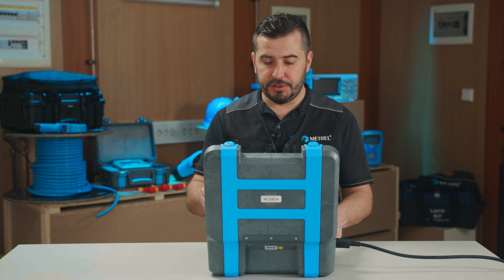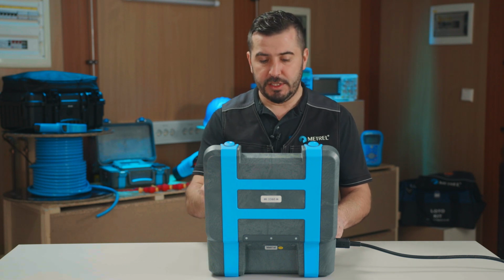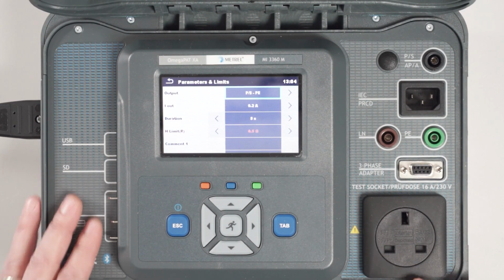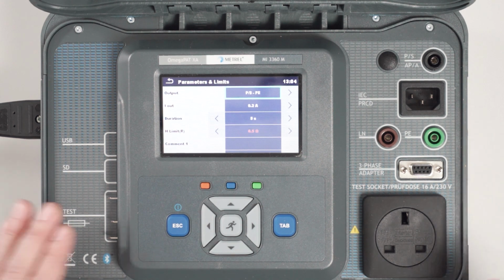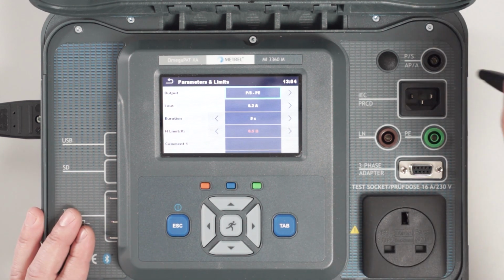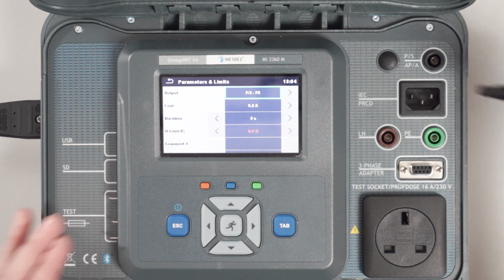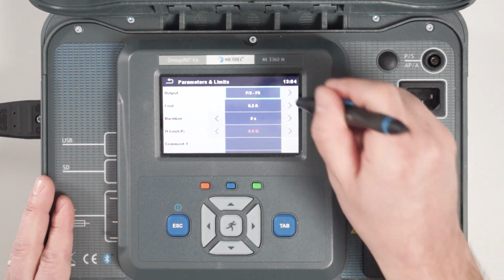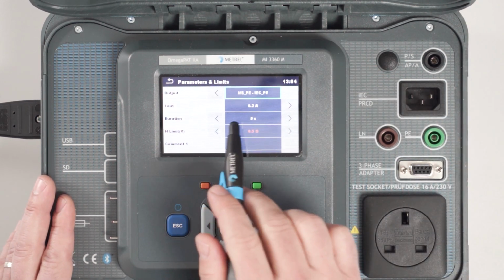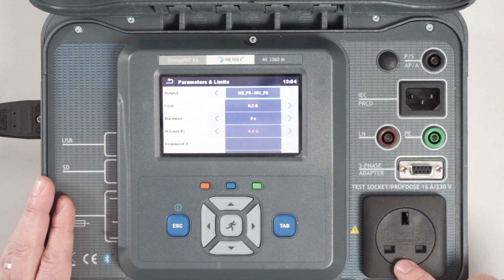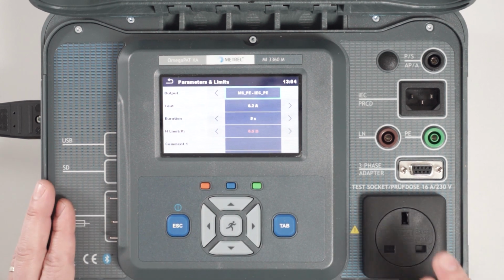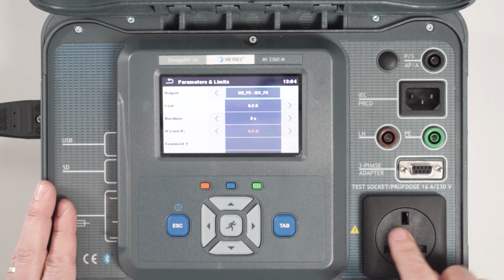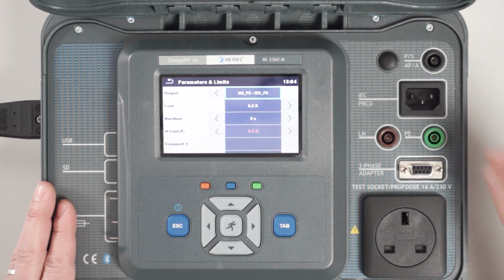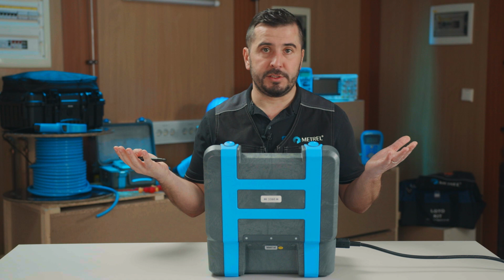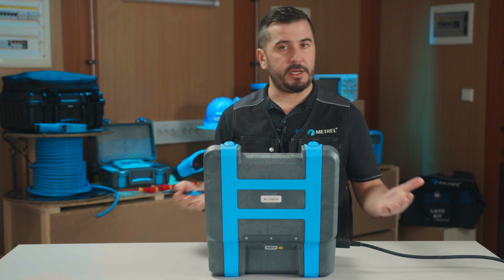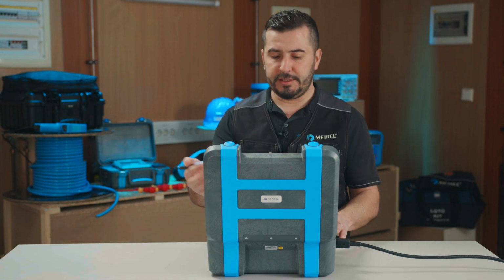So for the earth continuity, we have the following options. We can choose whether we would like to test earth continuity between main socket and this PE probe test terminal, or we can choose the MS PE - IEC PE. This means that the earth continuity will be measured between the main test socket and the IEC port. So this is applicable for testing of extension leads or IEC leads.